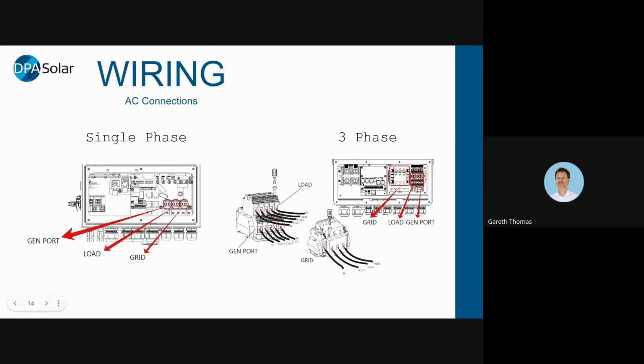The AC wiring on the single phase looks like what we've got on the left-hand side here. So you've got the auxiliary or the generator port on the far left. Then you've got the load or the output in the middle here, and then the grid input on the far right here. In the 3-phase, it's a little bit more confusing. You've got the grid input on the left-hand side here, and then the load and the auxiliary input are stacked on top of each other like this. So the load is the top level, and the auxiliary or generator port is the bottom level there.